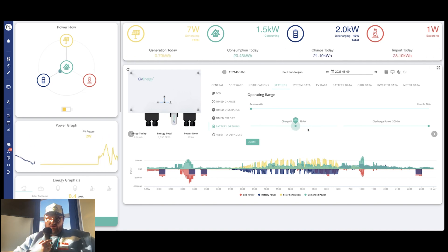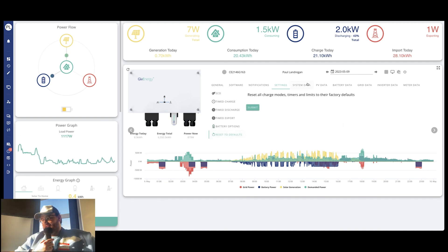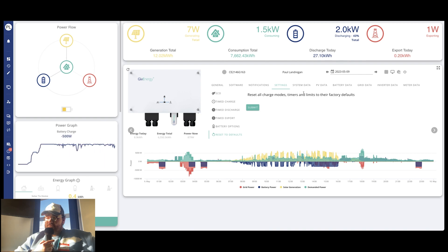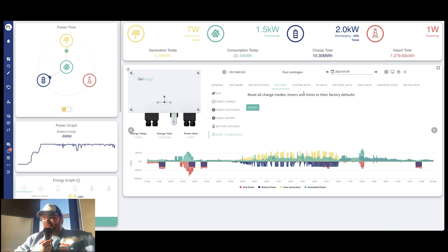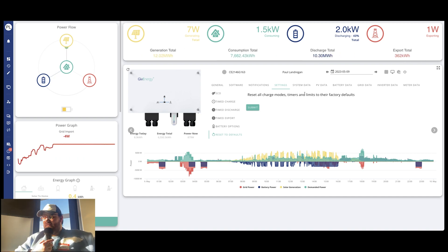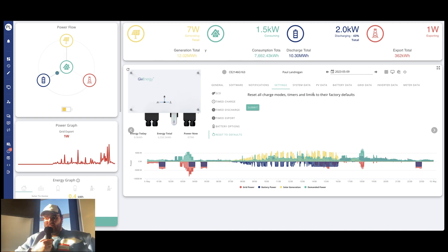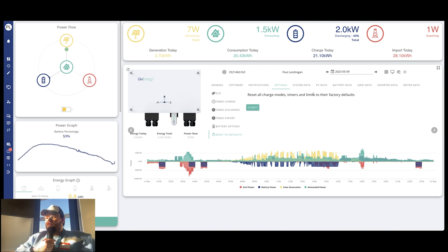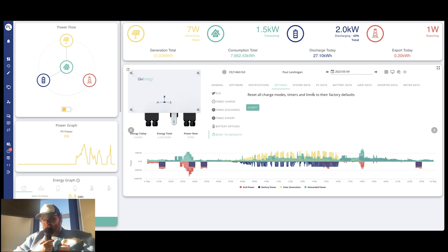We went through that on the app guide that we did. Anyway, one thing that's really, really kind of important, I think to note as well, the reset to defaults. The amount of times that we have people accidentally breaking their system from meddling and it would be because they've put a reserve on that they've not realized, that they've changed something that's not really clocked. If ever, and this probably is one for the installers to be honest, if ever you have a customer calling up where the system's not working properly, it's not discharging or charging like they'd expect it to, just click that first. Nine times out of 10, that will resolve the issue. And if it doesn't, then obviously you can elevate it to us, but that's a good little first step that you could do.